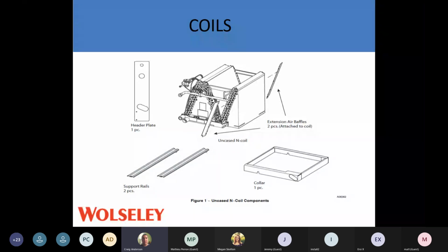Put your channels in, set this plate on top, make sure that right-hand side is not blocked. If that right-hand side is blocked, you're going to start your air conditioner, it's going to run for 15 or 20 minutes, everything's going to look hunky-dory. You're going to put your tools away, wave to the customer and leave the yard. That afternoon, they're going to call you because that air conditioner is frozen up. It will slowly freeze the right-hand side of that coil till the whole coil is frozen.